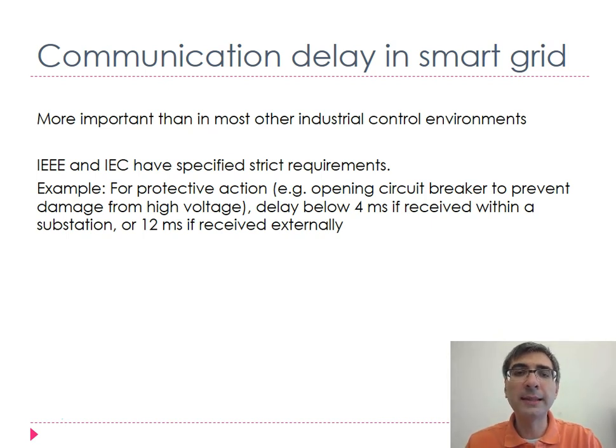If it's communication inside a substation, then for protective action the delay should not be higher than 4 milliseconds. By protective action I mean something critical, like opening a circuit breaker to prevent damage from high voltage. If received externally, it should not be over 12 milliseconds.